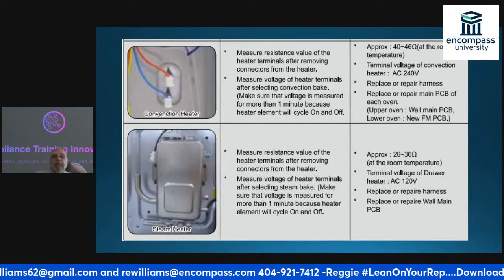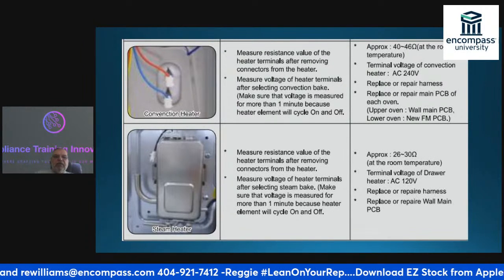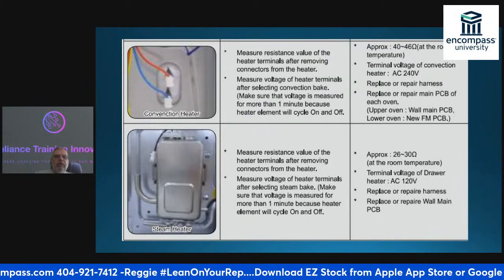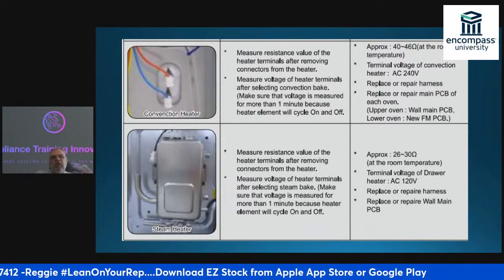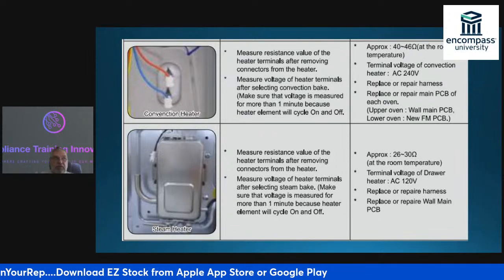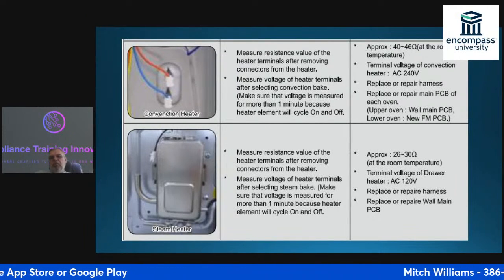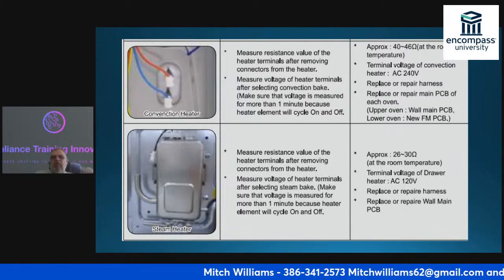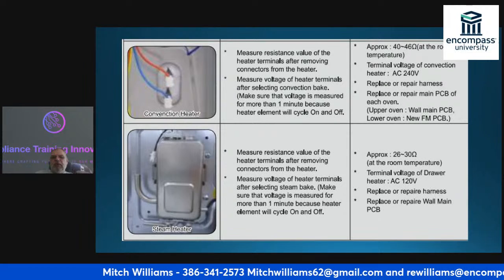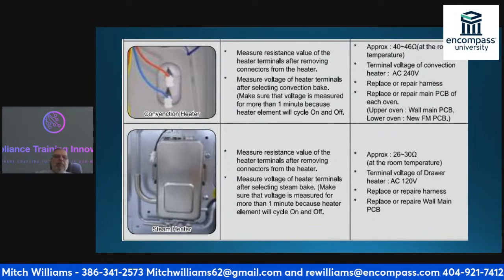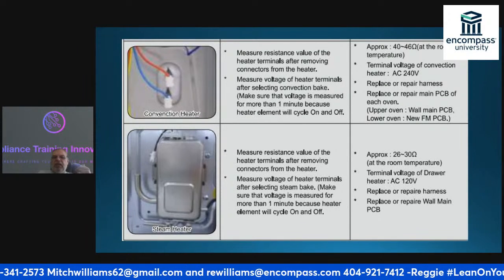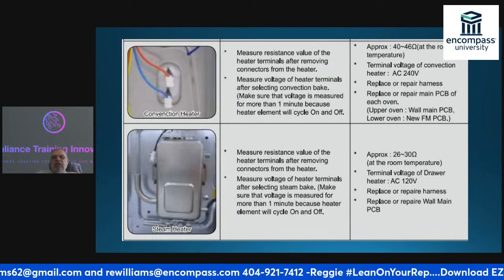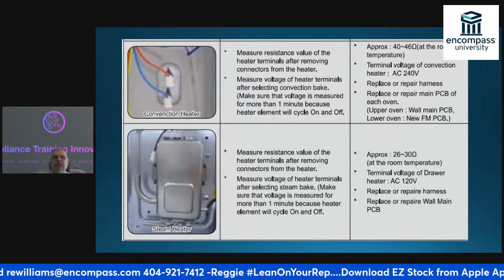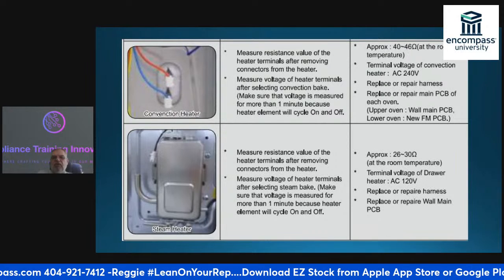So for my convection heater, once again, I'm going to unplug it and turn it off at the breaker. Then I'll measure the resistance, checking for between 40 and 46 ohms at room temperature. If it works, I'll plug it all back in, and then check to make sure I've got 240 volts.